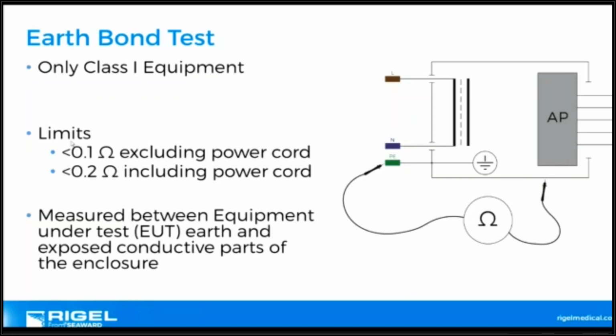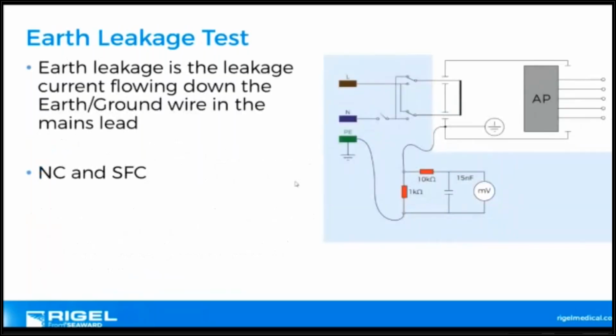And we've got some safe limits within 60601, various limits, different standards. Earth leakage current. What is earth leakage current? We've discussed it many times. But again, if I've got my functional current flowing here to here, this is 100 milliamps flowing in, and I've got 99 here. Well, due to stray capacitance or dielectric resistance, it's escaping this system, and it's flowing through the device, through my protective earth, through my measuring device, which is the body model, back to ground. So that's how we would measure the fault current within the device, and that's what leakage current is.